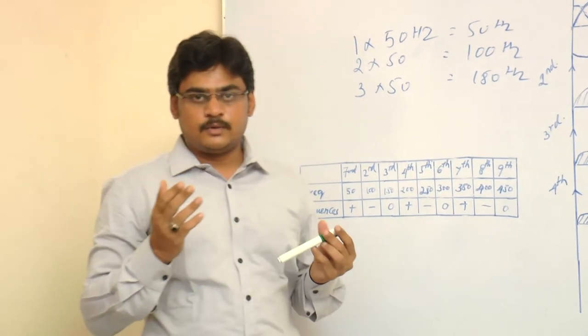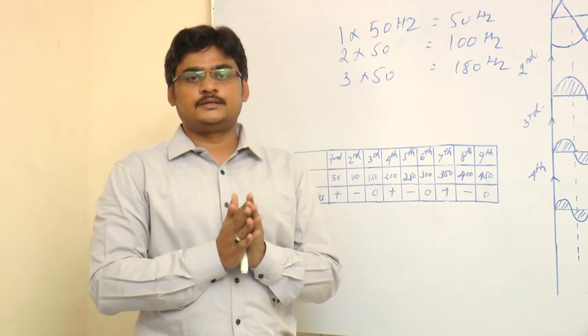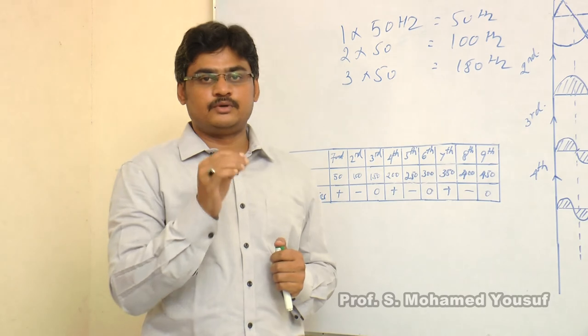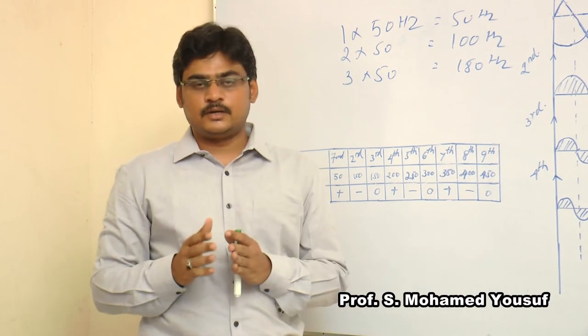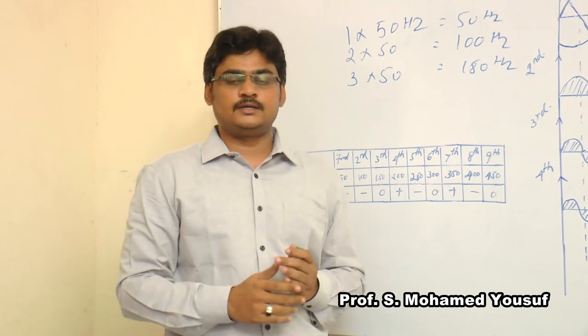Now I will tell you how to minimize harmonics in power converters. Normally voltage harmonics mainly depend on the source and can be minimized by using input impedance. Current harmonics are mainly because of non-linear loads and can be minimized by using LC filters.